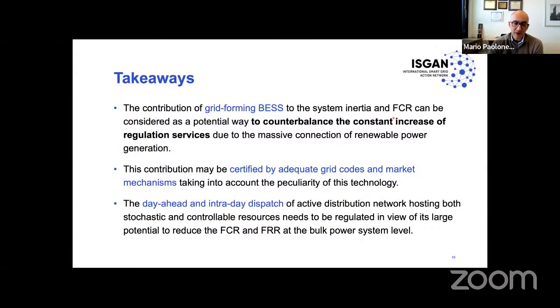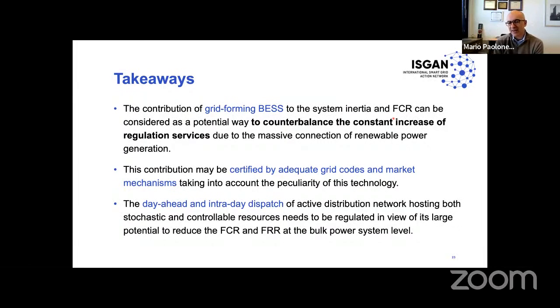So there are essentially three takeaways. First, we can consider grid forming battery energy storage systems as effective assets to provide inertia and frequency control reserve, as well as absorb stochastic aspects at the local distribution level, which is always beneficial in terms of compressing frequency containment reserves at the bulk level. This contribution from local batteries may need to be certified by adequate grid codes and market mechanisms that at the moment are rather primitive, and that have to take into account the peculiarity of this technology. I think there is a long path to achieve this.